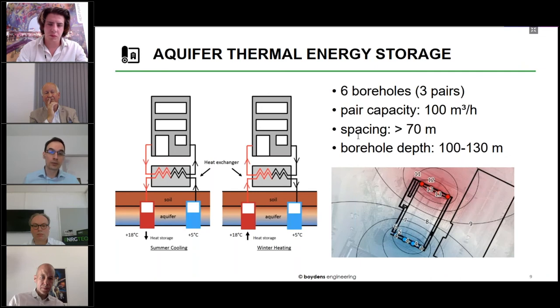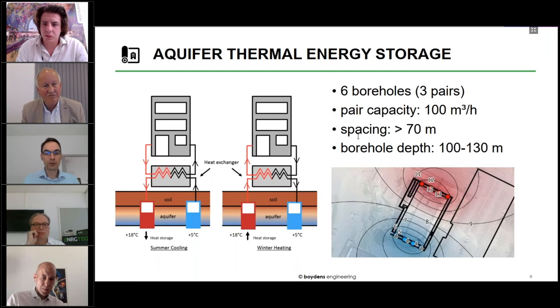Now, since we are quite close here to the Dutch border, and the soil properties and the aquifer properties are quite good here, we can extract a lot of flow just through one borehole. So you can see here on the bottom right picture an example of how, locally on the east side of the wells, a zone of cold and hot storage is created. So it's a ground aquifer temperature which is elevated or which is decreased locally. This is not from this project, but just to illustrate.